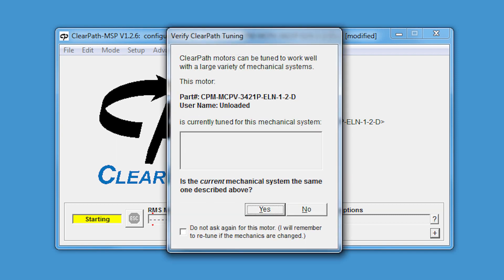Well, ClearPath motors can be tuned, in other words, optimized for the specific mechanics that they're attached to. When the motors are shipped from Teknic, their tuning parameters are set up for unloaded motors. This means that they're tuned for running with no load. If you attach mechanics to the motor, or change the load in any way, you're going to want to retune the motor to optimize its performance.